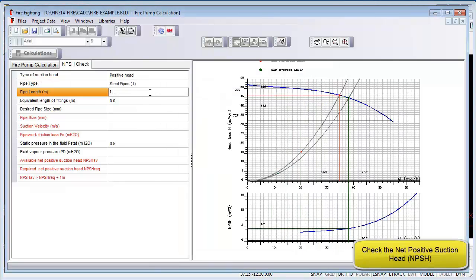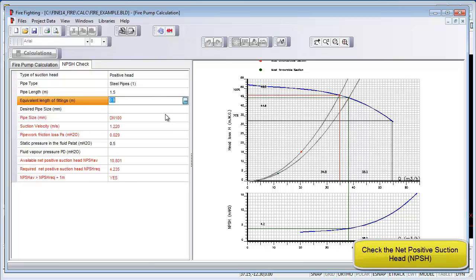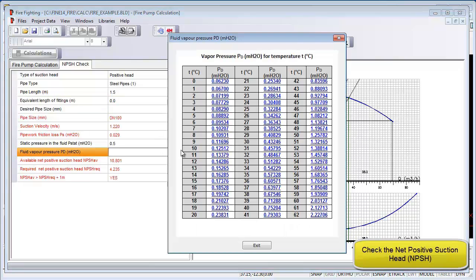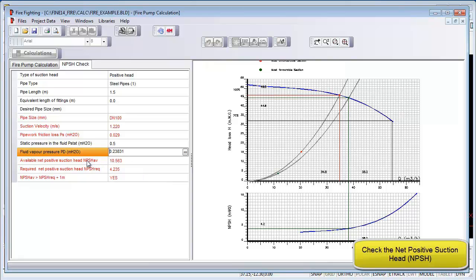The last row of the table will tell you if your design complies for NPSH or not. In this case, it does comply.